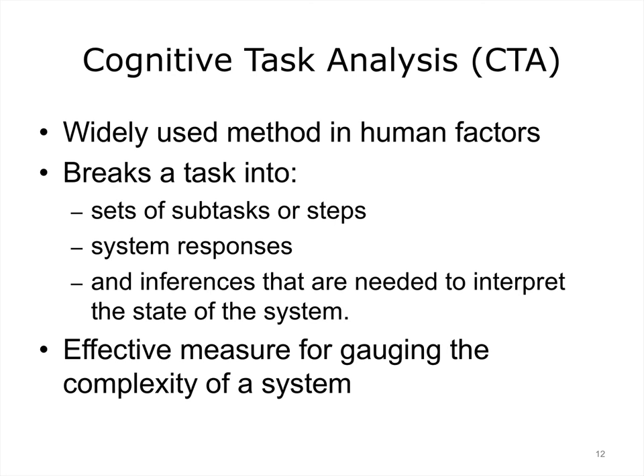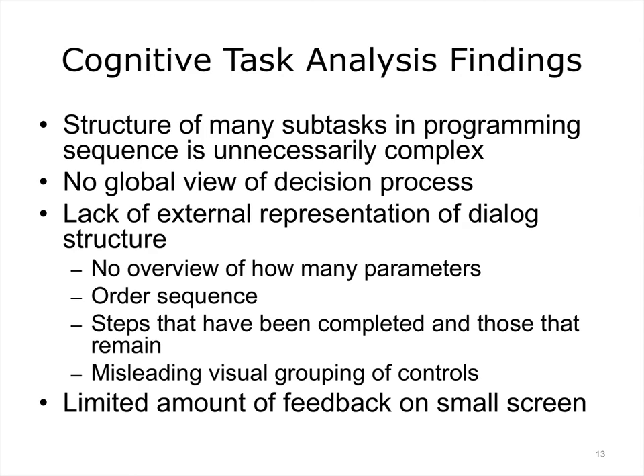For example, a simple task that necessitates 25 steps or more to complete using a given system is likely to be unnecessarily complex. On the basis of the Cognitive Task Analysis (CTA), Lynn et al. found the existing PCA interface to be problematic in several ways. The structure of many subtasks in the programming sequence was unnecessarily complex. There was no overview of the entire task and a lack of external representations to guide the user — for example, a nurse would not know that he or she was on a third of five screens and was halfway through the task. The grouping of controls was very confusing, with some buttons serving two functions.